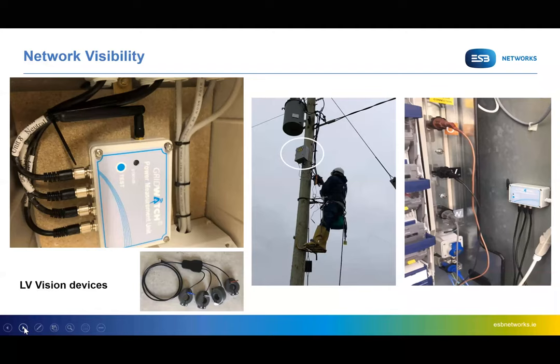So we've installed a technology in our ground mounted substations and at our pole mounted transformers to provide data for analysis and to really understand what's happening on the network. So across the network as a whole, there's 30 locations where we've installed these low voltage monitors. And one of my later slides shows data from the monitor, and you can see some of the things that you can actually find out.